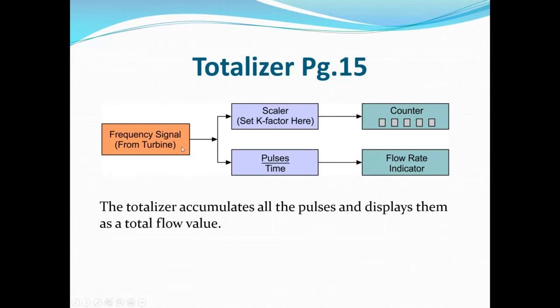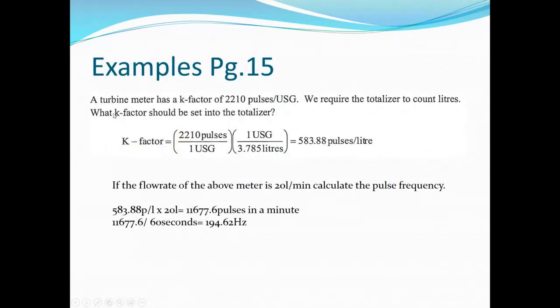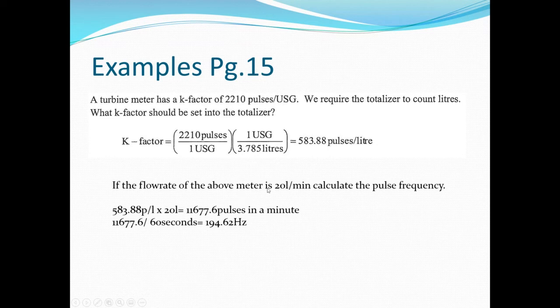Now for totalizer math: a turbine meter has a K-factor of 2,210 pulses per US gallon. To convert to liters: divide 2,210 by 3.785, giving 583.88 pulses per liter as the new K-factor. If the flow rate is 20 liters per minute, the frequency is 583.88 times 20 equals 11,677.6 pulses per minute. Dividing by 60 gives a frequency of 194.62 hertz.